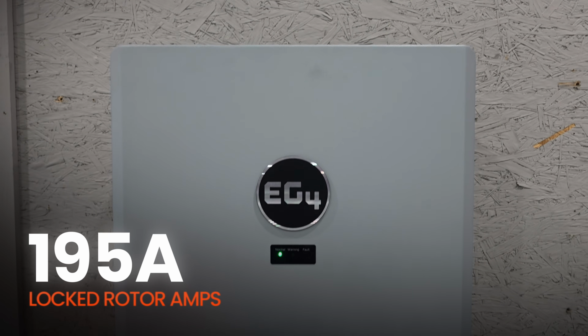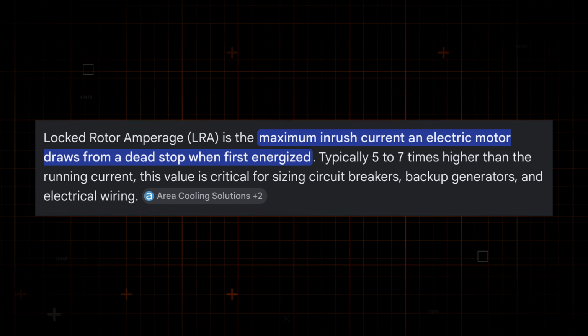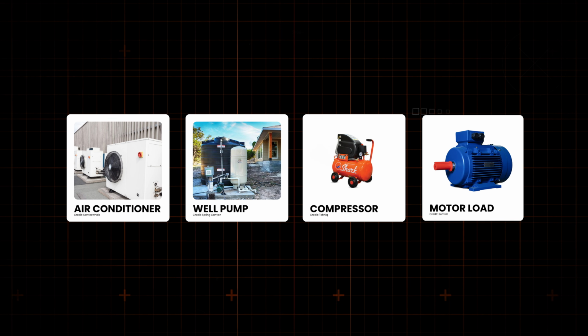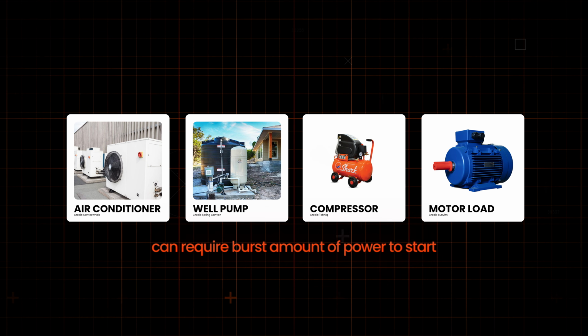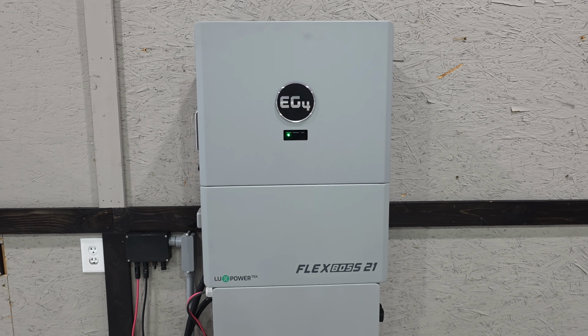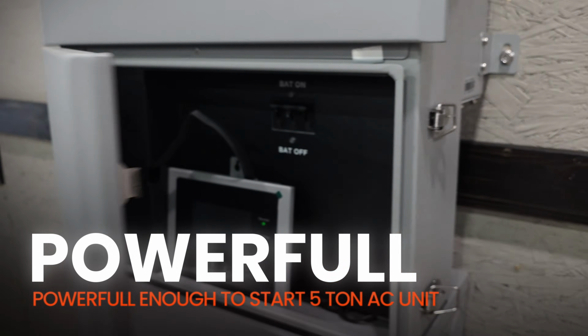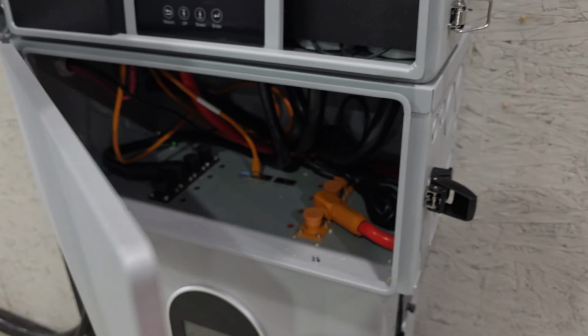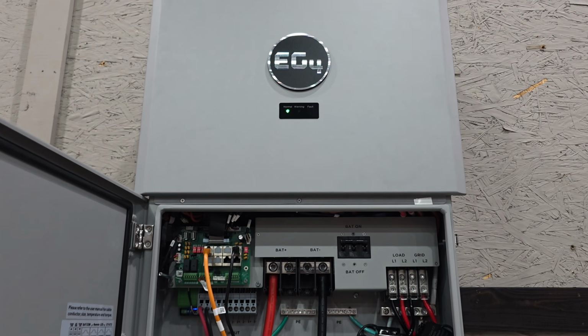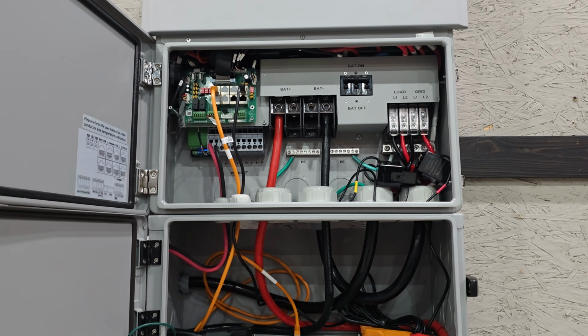The other big number that stands out is the locked rotor amp rating. EG4 lists this at 195 amps. That's important because starting motors is very different from running motors. A large air conditioner, well pump, compressor, or motor load can require a much larger burst of power to start than it needs once it's already running. And that is why the locked rotor amps matter. EG4 says that the FlexBOSS 21 is powerful enough to start a 5-ton AC unit. And for a lot of people looking for whole home backup, that's a very big deal, because the moment you start talking about running central air conditioning, you're no longer talking about a tiny backup system. You're now looking into a category where inverter output, surge capability, battery sizing, wiring, and system design are all really something you need to consider.